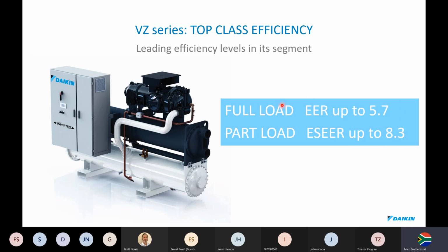You'll notice that water-cooled chillers are always more efficient. I'm talking chiller only. This is why these values are so much higher than air-cooled, for the simple reason we don't have fans spinning here, so we use less electricity. This excludes the cost of the pump running, which you'd need going to your cooling tower fan. But as for the chiller itself, Daikin will only supply you the chiller. The third party would be the pumps and the cooling tower fans, etc. But from an efficiency point of view, we are very, very efficient in the market, up to 8.3 on seasonal energy efficiency, which is very, very good performance.